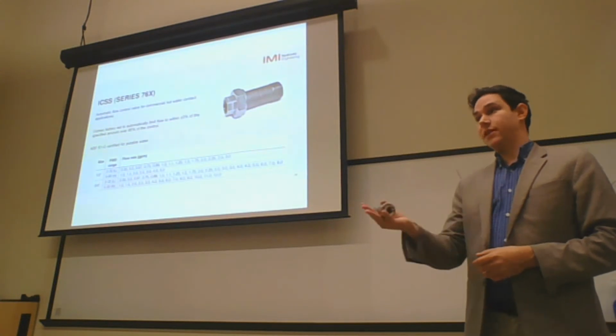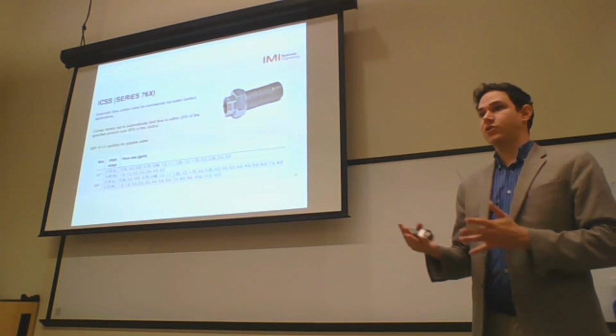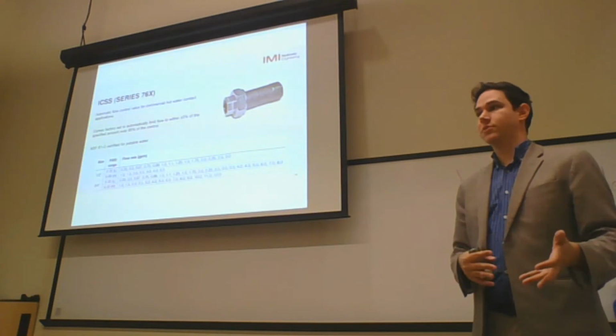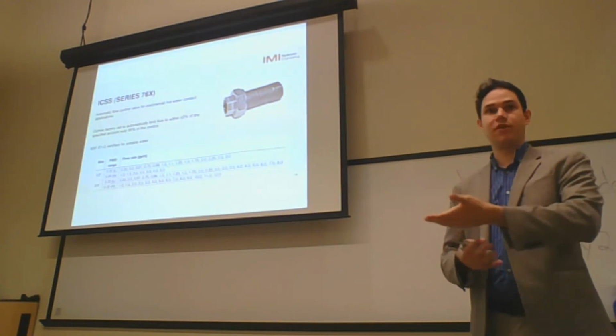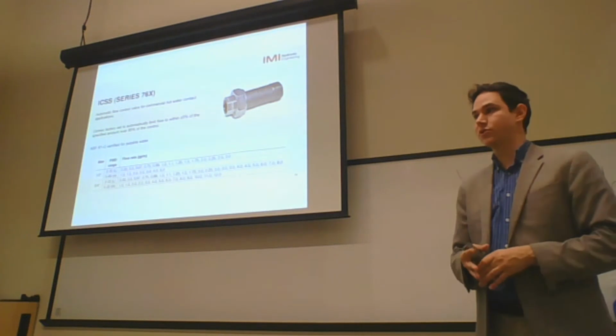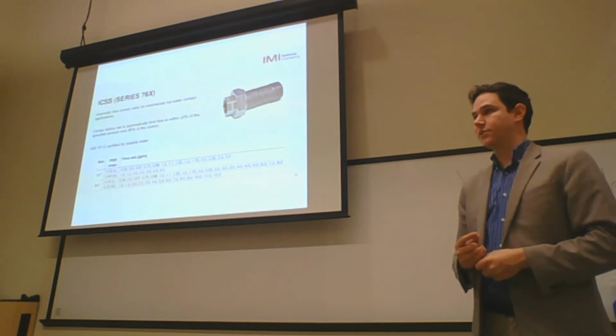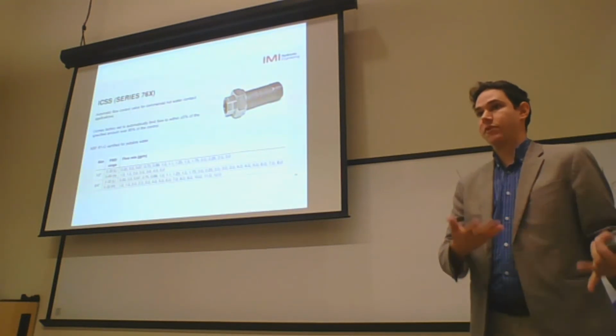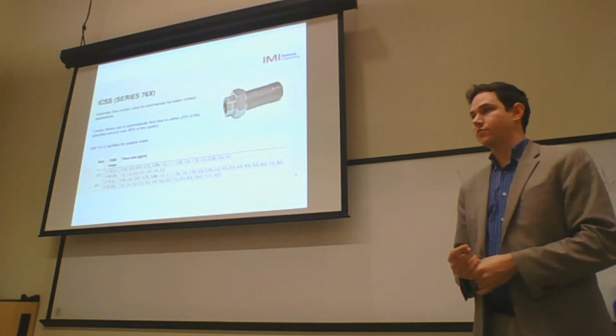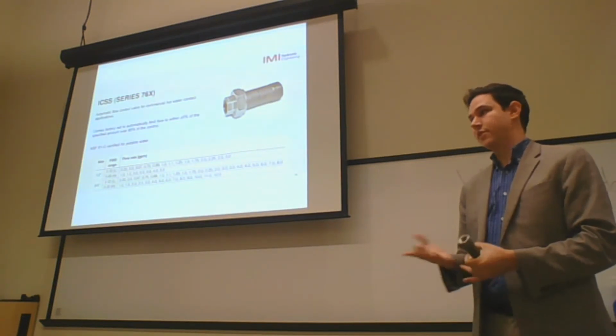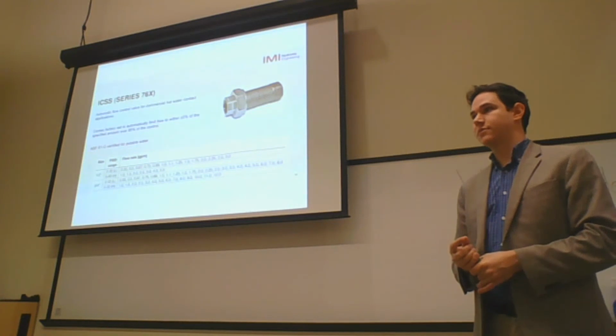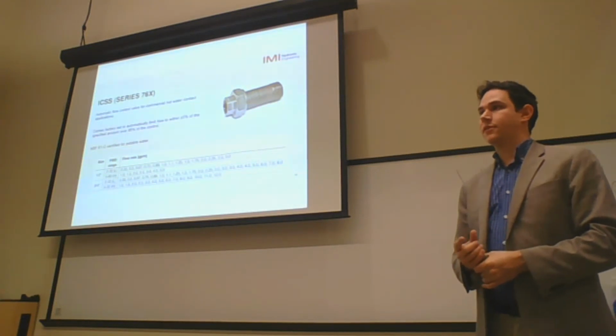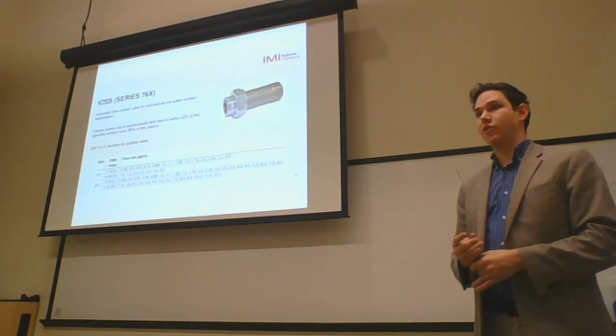Another option, if you want to take a more precise measurement, if that is your concern, I would go with the globe style. Globe style is the one that most of you are used to in the day-to-day as well. The same as a TA valve, now it is lead-free. So just changing the material of the body, but you have the most precise measurement on that, and balancing through the flow rate.